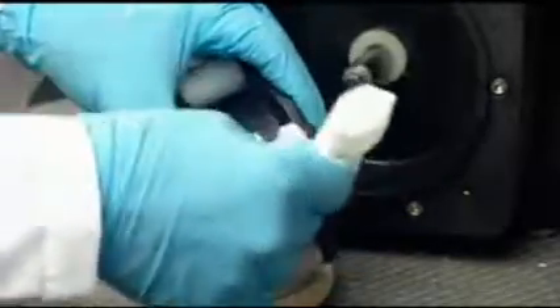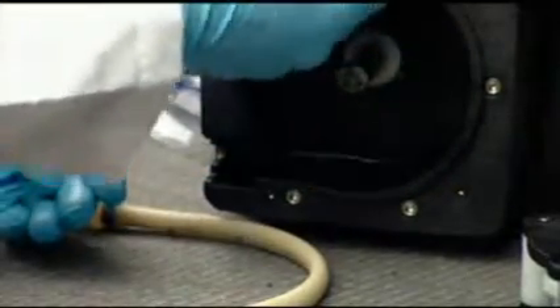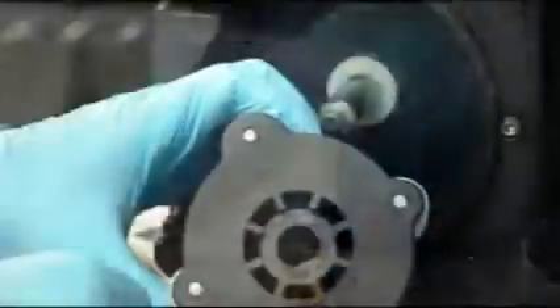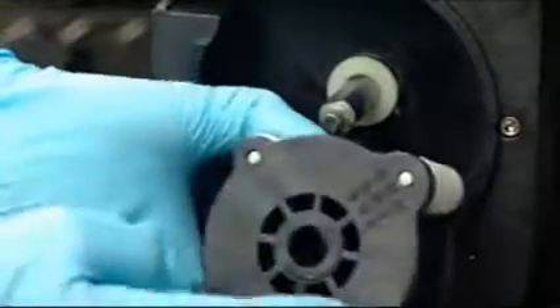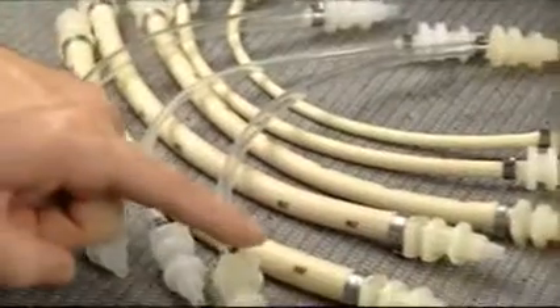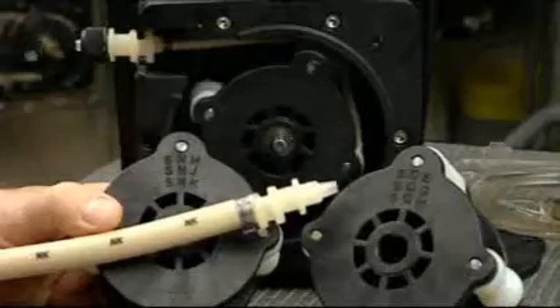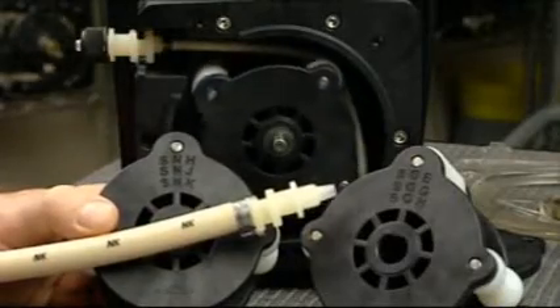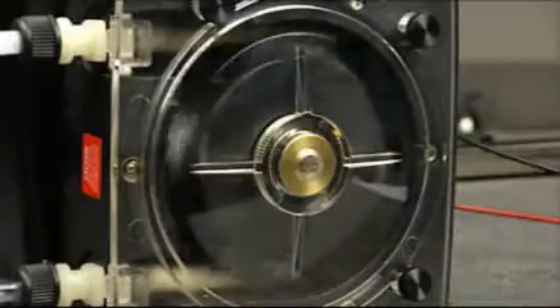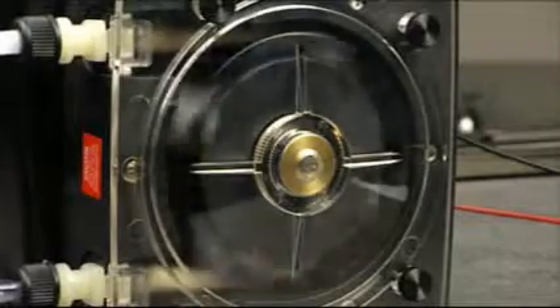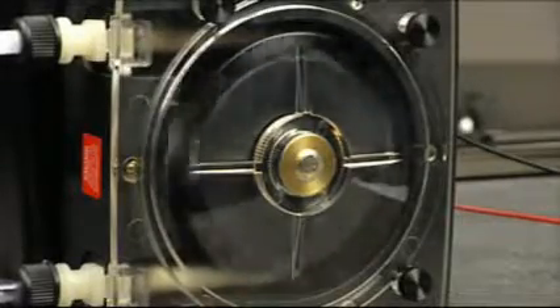Inspect the roller assembly. If chemical has come in contact with the roller assembly, wipe the assembly with a damp cloth and dry thoroughly. Inspect the pump head. Wipe clean any chemical or debris from the inside of the pump head and TFD sensor pins. Locate the front side of the roller assembly. Due to the various tubing wall thicknesses, 3 different roller assemblies are offered, each with different roller diameters. The correct roller and pump tube assembly combination must be used to properly squeeze the pump tube.